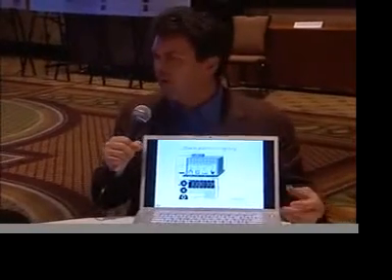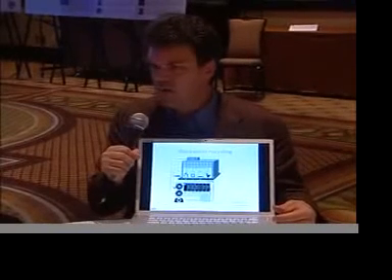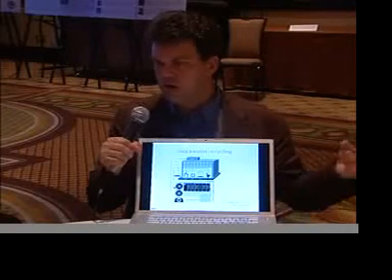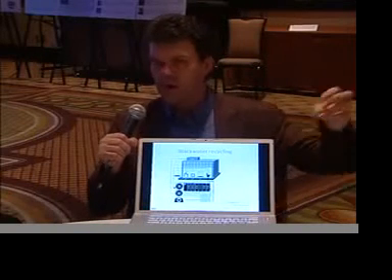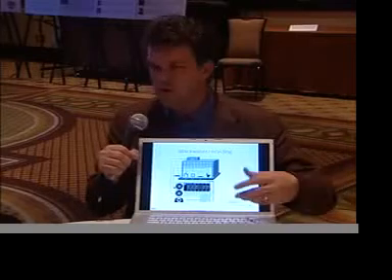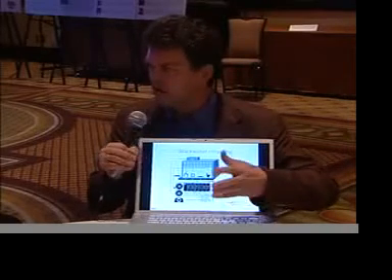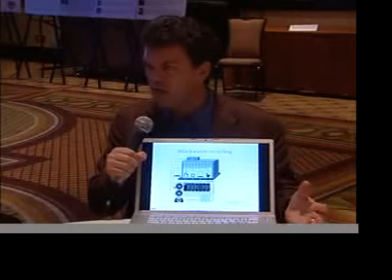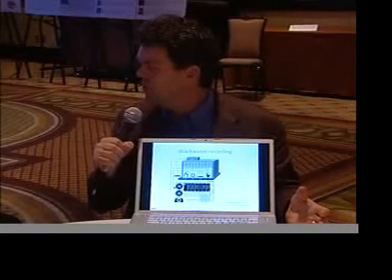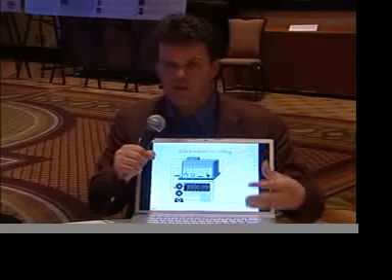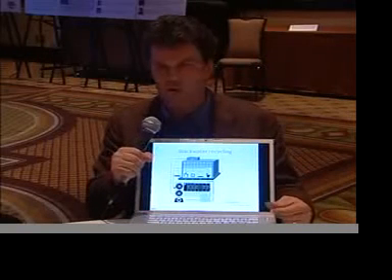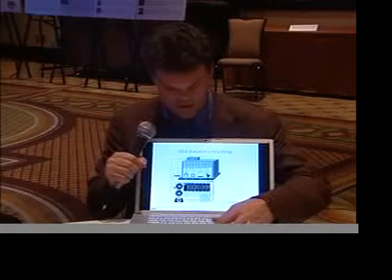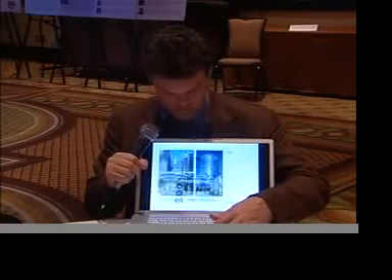The challenge is to make it affordable, which means you really have to design it from the ground up. What we've seen over the years is that municipal scale schemes have been scaled down for this application. When you've got the sewer as a backup, you can remove a whole lot of redundancy. You can take the system down for maintenance, which you don't have the luxury of in a municipal sewage treatment plant. So these are the design philosophies that we introduce, just to cut down on the cost. It's about being practical, really.